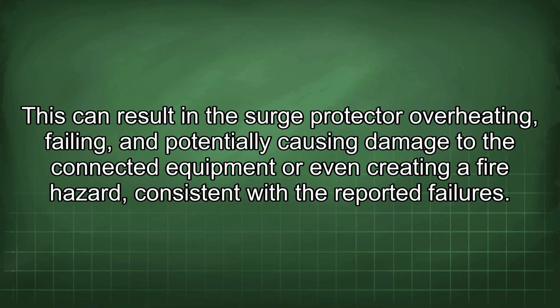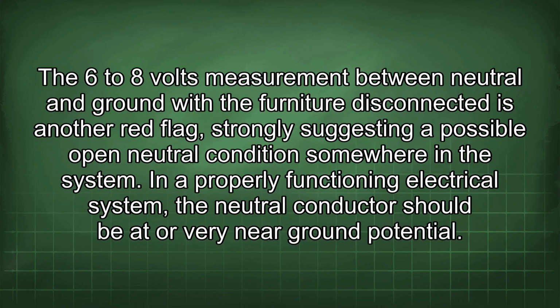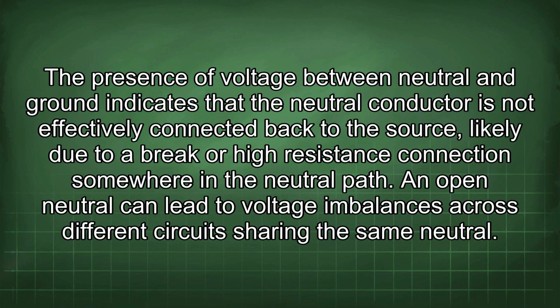This can result in the surge protector overheating, failing, and potentially causing damage to the connected equipment or even creating a fire hazard, consistent with the reported failures. The 6 to 8 volts measurement between neutral and ground with the furniture disconnected is another red flag, strongly suggesting a possible open neutral condition somewhere in the system. In a properly functioning electrical system, the neutral conductor should be at or very near ground potential. The presence of voltage between neutral and ground indicates that the neutral conductor is not effectively connected back to the source, likely due to a break or high resistance connection somewhere in the neutral path.